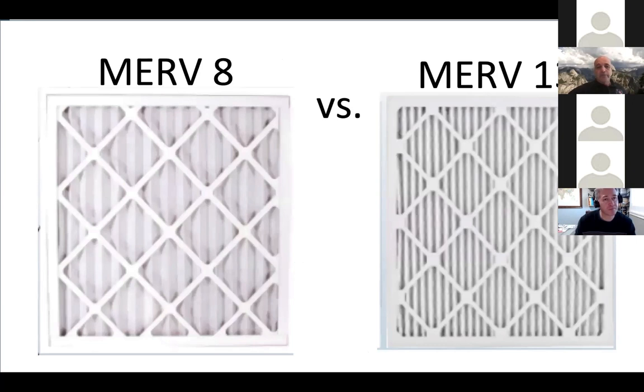So what's the difference between a MERV 13 and a MERV 8? In the picture here, you see a MERV 8 on the left. It has roughly 12 to 13 pleats in it. And then the MERV 13 has usually 24 to 26 pleats. So there's twice as much surface area for capturing particles. Because the MERV 13 filters out much smaller particles in the air, it requires a much larger surface area to be able to handle the airflow. So you can buy good quality MERV 13 filters that will actually have a lower pressure drop than some of the cheaper MERV 8s. So it doesn't really impact your equipment as much as some people are concerned with.